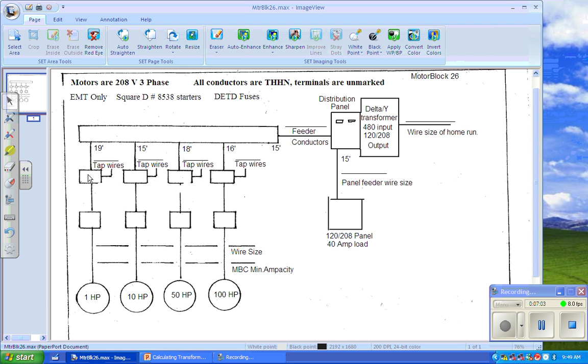And if we use 16 wire, we can go all over the place. As long as we have a fuse, it's 10 amp. So we'd have to have a fuse holder that's a 10 amp fuse holder coming from the supply circuit on the load side of one of these fuse disconnects. Everybody understand that now? And so we'd run around with our control circuit, and it would be fused at 10 amps, and we could use number 16 wire.